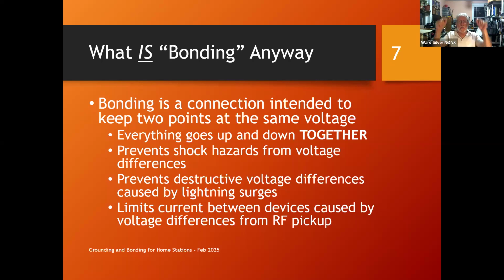If you have the same voltage at these 2 points, you won't have any current flowing between them. Current flows because of a potential difference. If you've got a voltage over here and a voltage over here, and there's a connection, then current will flow from the high voltage to low voltage. And so what we want to do is minimize this current flow, because that's what causes interference. You also prevent shock hazard from voltage differences. If you bond everything together and that's connected to your AC safety ground, then if there's a fault in insulation, if something is a short circuit, who knows, then by bonding everything together and then connecting it to your AC reference point, you prevent shock hazards.